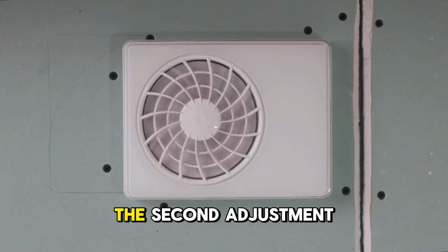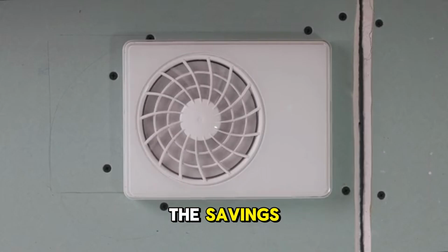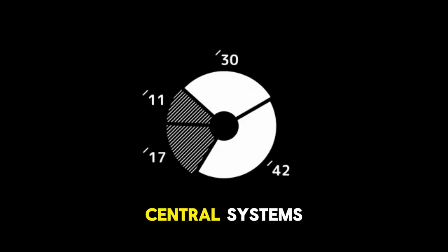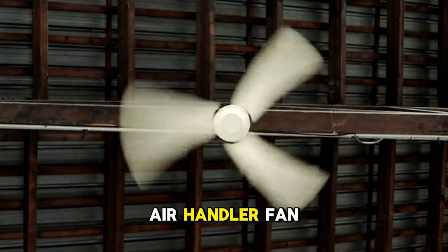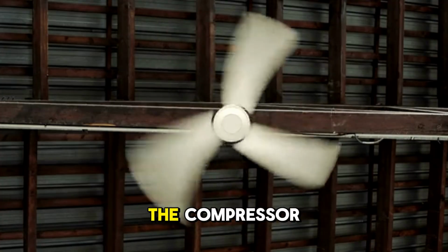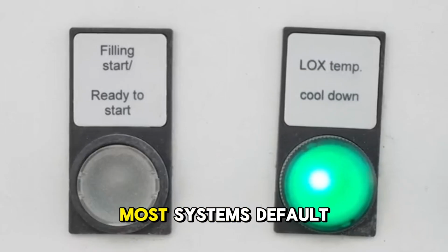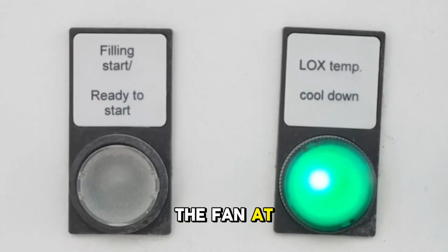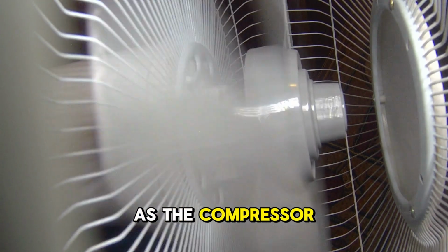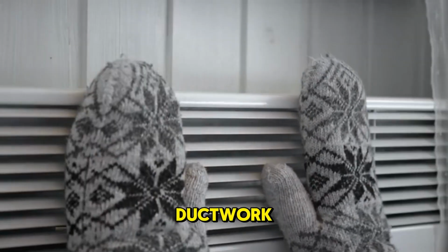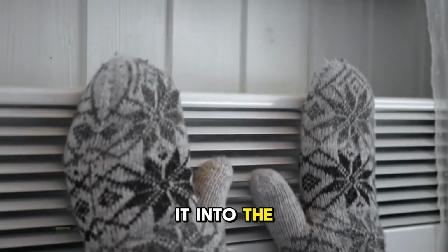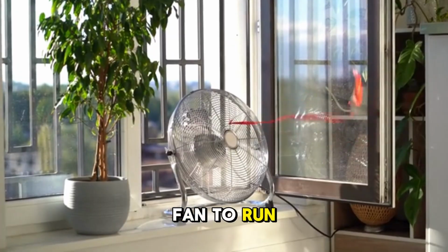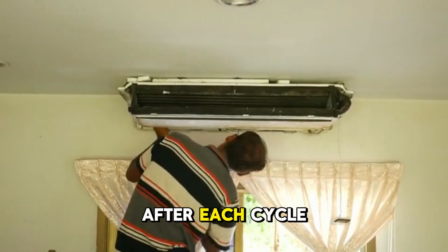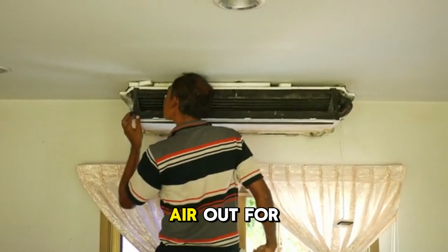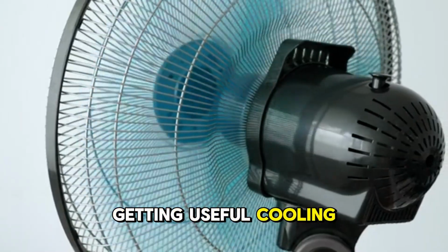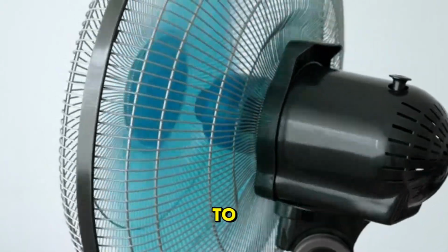The second adjustment that adds to the savings is the fan delay setting on central systems, which controls whether the air handler fan keeps running briefly after the compressor shuts off. Most systems default to stopping the fan at the exact same moment as the compressor, which leaves cold air sitting in the ductwork instead of distributing it into the rooms. Setting the fan to run for 60 to 90 seconds after each cycle pushes that residual cold air out for free, getting useful cooling from air the compressor already worked to condition.